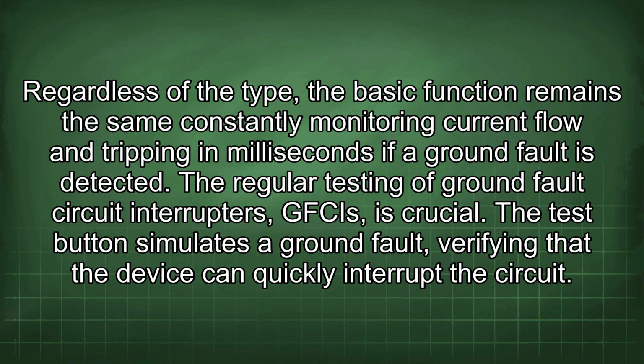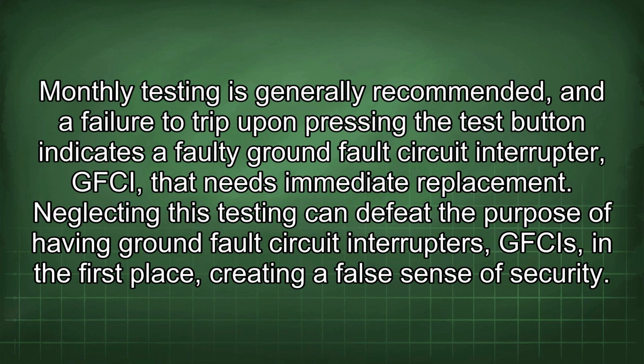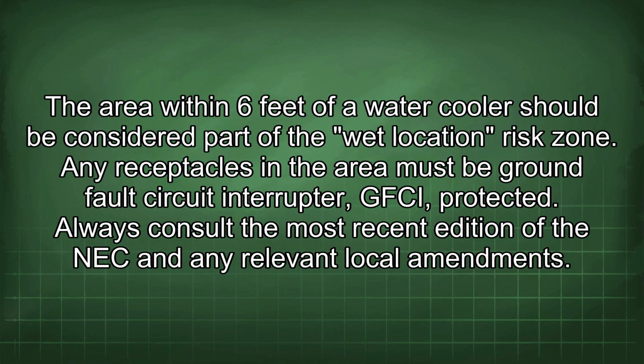The test button simulates a ground fault, verifying that the device can quickly interrupt the circuit. Monthly testing is generally recommended, and a failure to trip upon pressing the test button indicates a faulty ground fault circuit interrupter (GFCI) that needs immediate replacement. Neglecting this testing can defeat the purpose of having ground fault circuit interrupters (GFCIs) in the first place, creating a false sense of security. The area within 6 feet of a water cooler should be considered part of the wet location risk zone. Any receptacles in the area must be ground fault circuit interrupter (GFCI) protected.